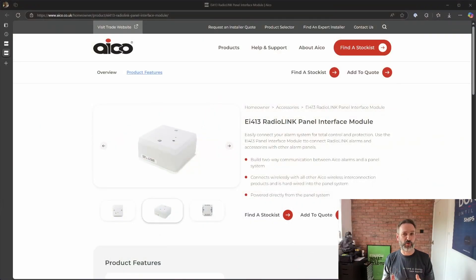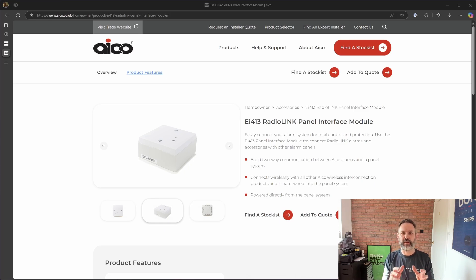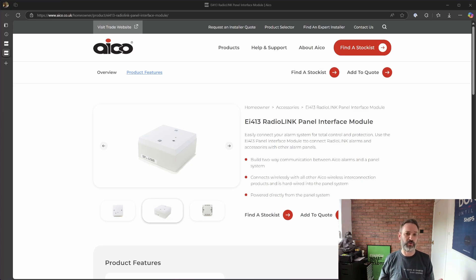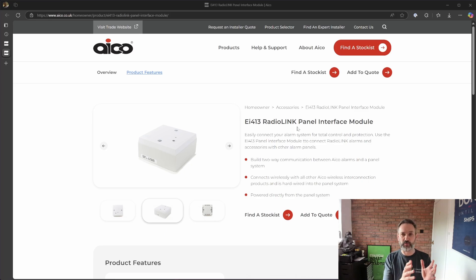Fast forward a couple of months and I came across the Aico stuff again — specifically the EI413 panel interface module. This module is designed to connect into an existing panel such as an alarm panel or a fire panel. I took a quick look at the installation instructions and it appeared to use relays for signalling the different conditions, and that makes it perfect for local control. Whilst this module uses something called Radiolink, which is an older version of the protocol, according to Aico's website it should be backwards compatible with SmartLink.